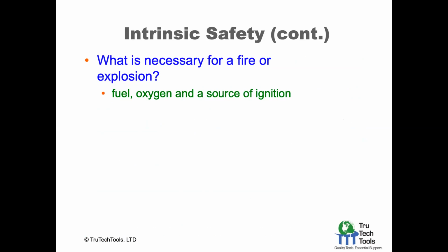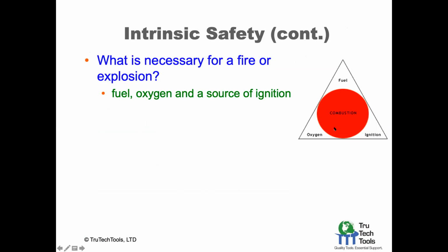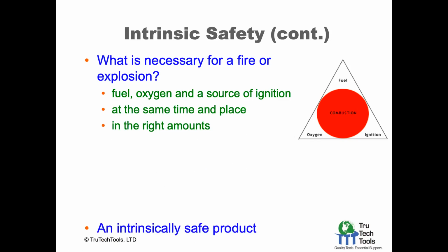So to get a fire or explosion, this goes back to your combustion safety training. Fuel, oxygen, and a source of ignition are required in order to get combustion. You need to have all three things present in the right ratios. We just talked about the explosive limits, which are a ratio between the amount of gaseous fuel and the oxygen that has to be present in the right range of concentrations, that red band in the little illustration we had earlier. And then the source of ignition, which would cause combustion to start taking place. So they've got to be in the same place, at the same time, in the right amounts.